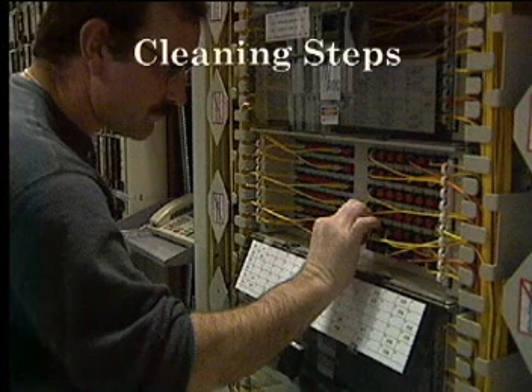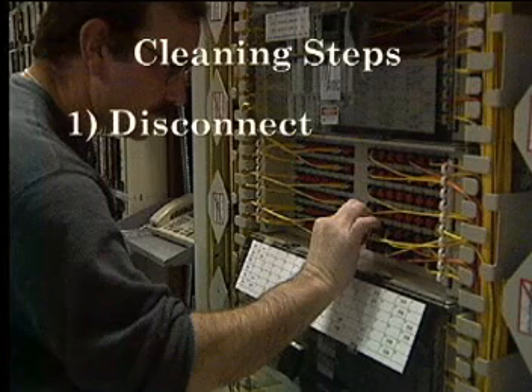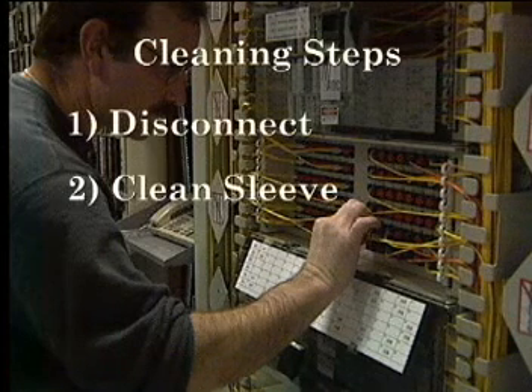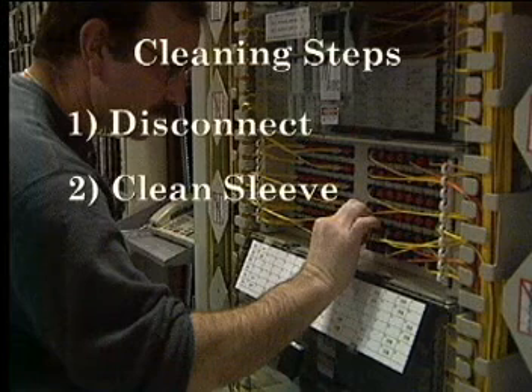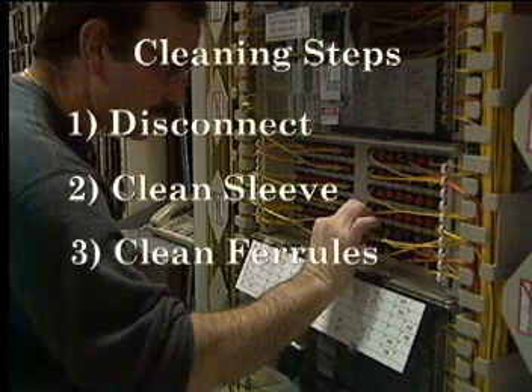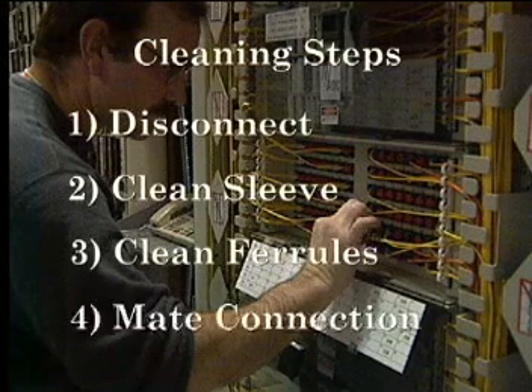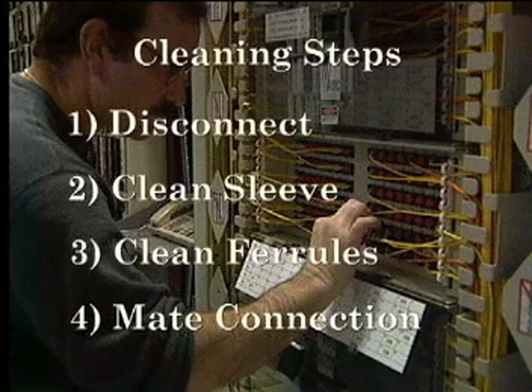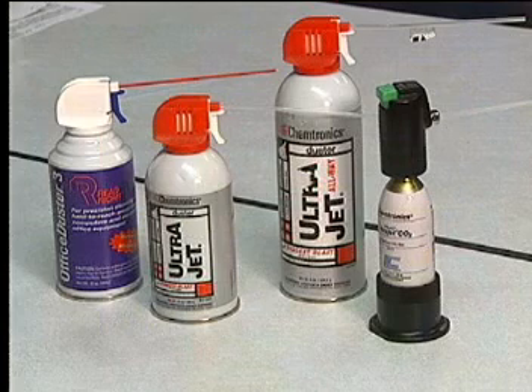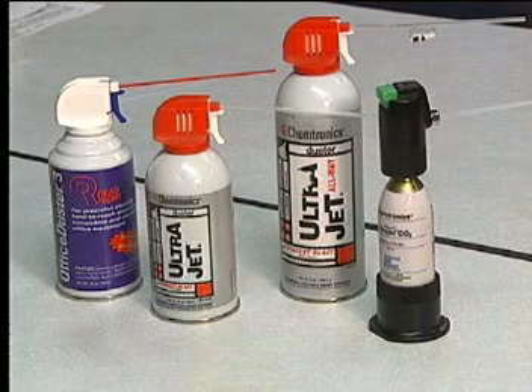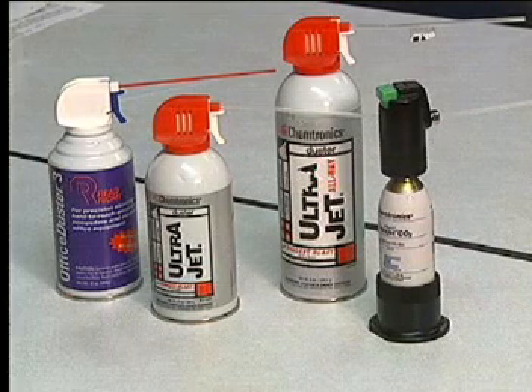are the same. First, connectors are disconnected from both sides of the sleeve. The sleeve is then cleaned to remove loose dust. Finally, both connector ferrules are thoroughly cleaned before the connection is remated. Once disconnected, a compressed gas duster is used to blow dust particles out of the bulkhead connector sleeve. Most of these products use a liquid propellant that produces a powerful blast of inert gas.